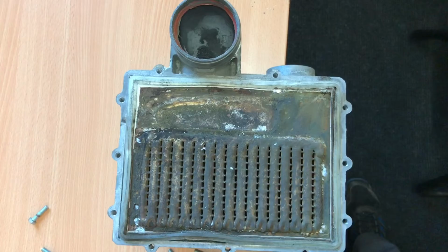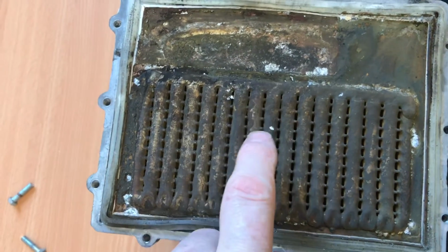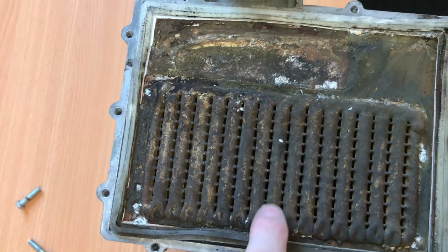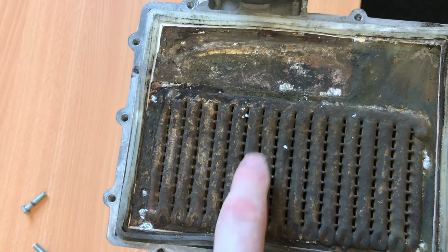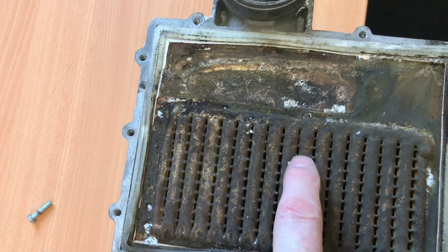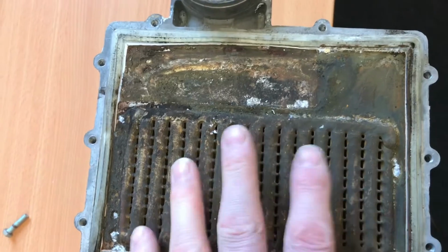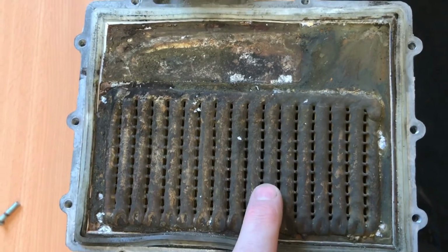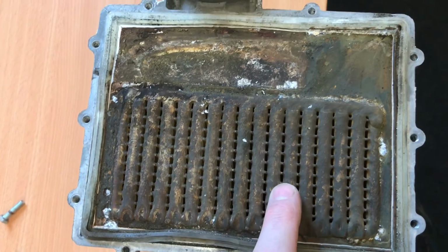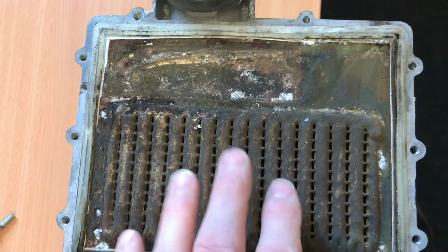Now I've taken the top off so you can see how this works. So the strips you can see here, this is where the products of combustion would be inside here, and the little holes is where the water would go through. So this is kind of the opposite way around, and the primary flue would be where the products of combustion would come through the little holes. So this aids it to take more heat out.